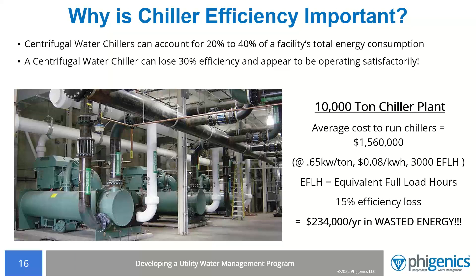Even with brand new chillers that collect reams of continuous data recorded somewhere in your building automation system or the chiller itself, you still find facilities maintenance personnel recording some of it on a clipboard. In addition, every chiller has alerts or alarms to warn you of serious problems, and everyone performs periodic maintenance.